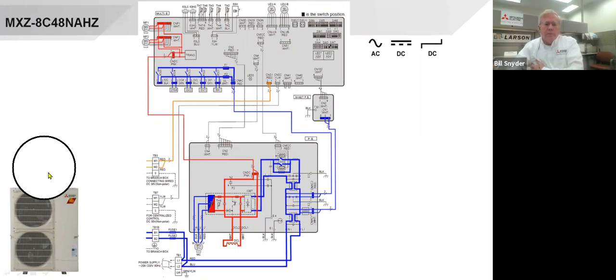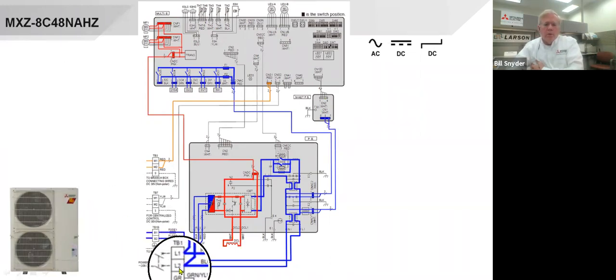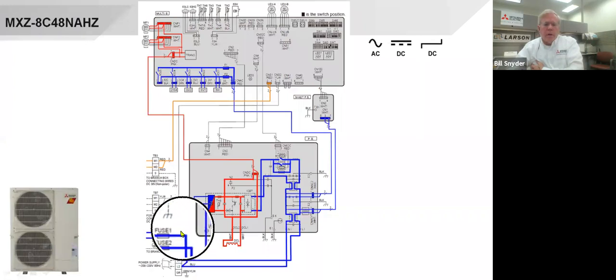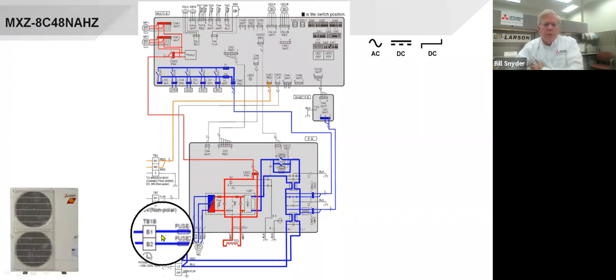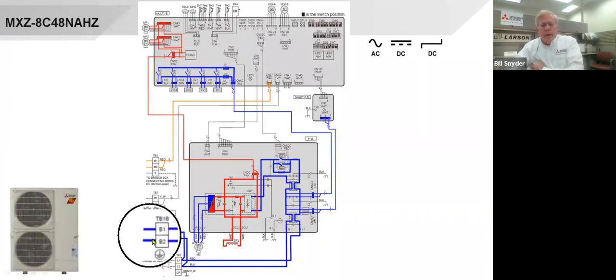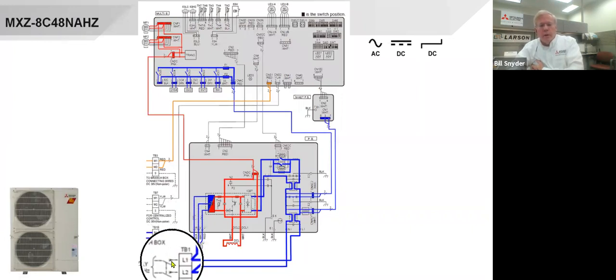So down here is your L1 and L2. It splits off and goes through 2 fuses and goes to these B1 and B2. That would be for your branch box. This is the unit that has a branch box, and we can put up to 8 indoor heads on this one outdoor unit. So if you ever find that the indoor branch box is not working, or none of the indoor units are working, but you do have power on L1 and L2, you might want to check those fuses.